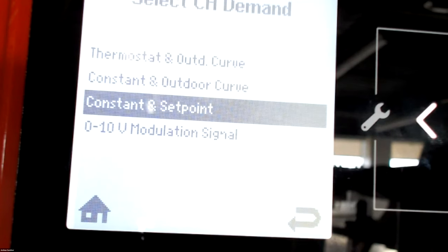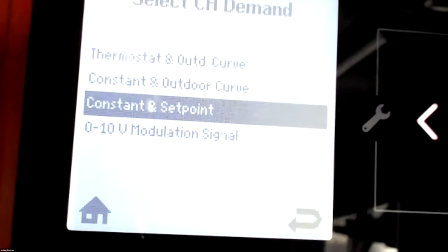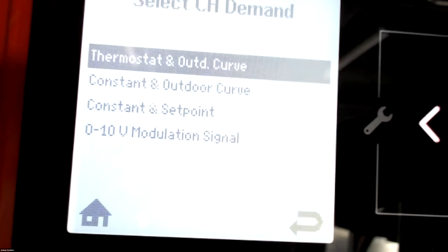If I unplug the outdoor sensor, I'm not going to do it, but if I unplug it, you'll see the options for outdoor curve go away. And all you'll have is thermostat set point, constant set point, and 0 to 10 modulation. So you'll lose those outdoor curve settings. As soon as it senses the outdoor sensor, it automatically pops up your curve options. So most of your applications are going to be thermostat and outdoor curve. We go ahead and click that.